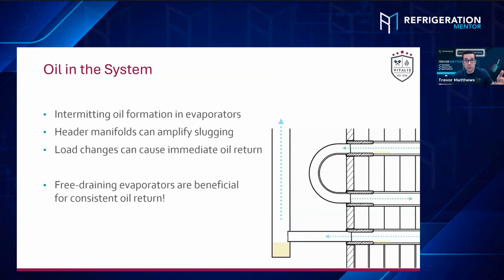We'll say in this one case we'll just not pull down, like if that one's full of oil versus the other one. What are some of the things technicians could check just to try to verify if it's oil or not oil, or how do I get that oil back from that case, for example? That's very difficult, because if you run into these issues, it's typically a field piping or design mistake, right? So it's very hard to fix that.